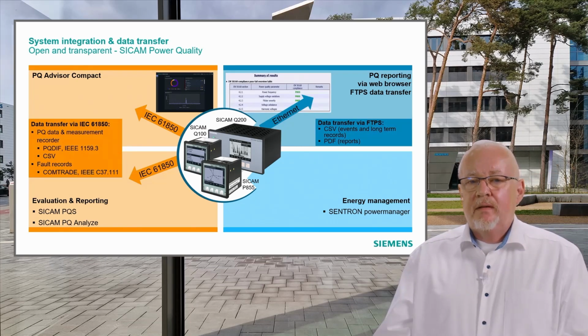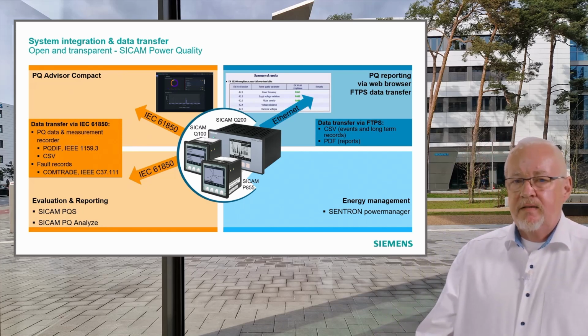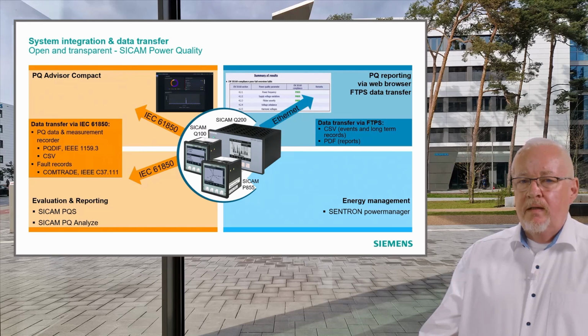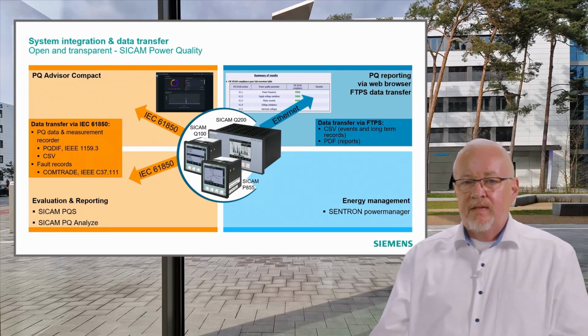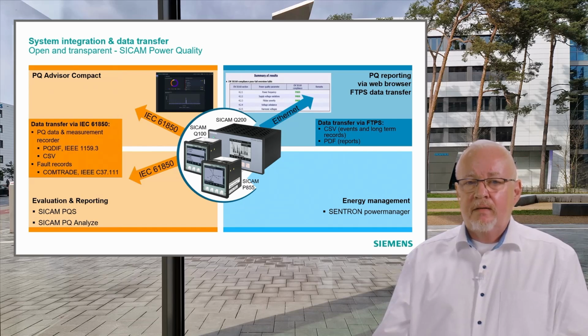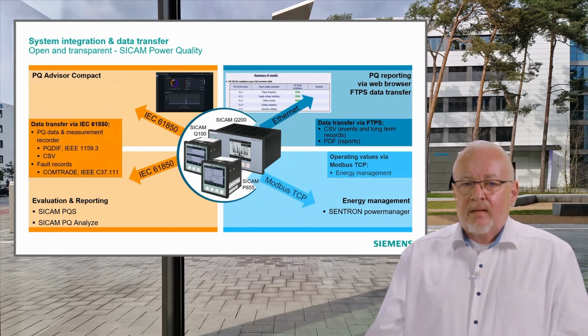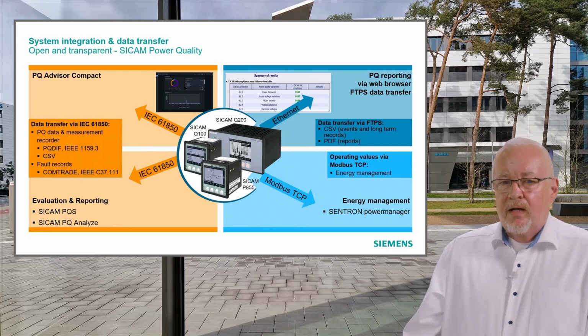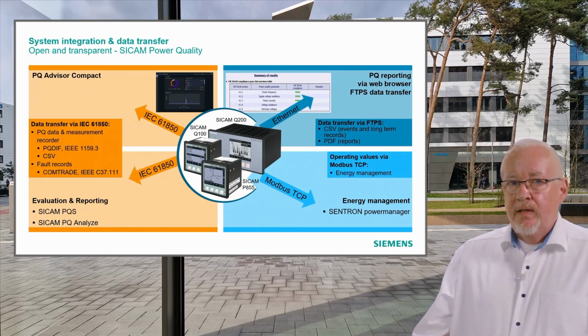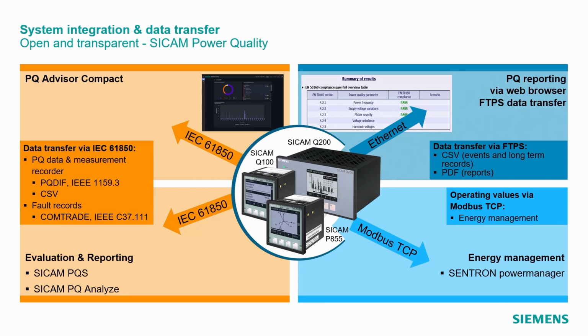On the other hand, we have the CSV file export via FTPS meanwhile, so that we can connect to other SCADA systems. If the customer doesn't like to use our software, he can import the long-term power quality reports as CSV files from the device and extract them and analyze himself. We have also other protocols which are mainly used in the energy management area, and that's Modbus TCP, and also the energy management from our EP department, Sentron Power Manager, and the Desigo CC from Building Technology will support power quality evaluations in next versions, also via IEC 61850 data transmission.